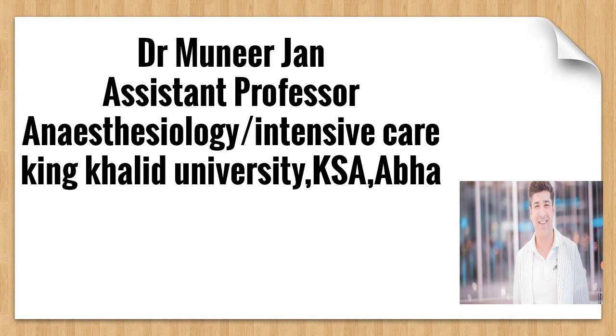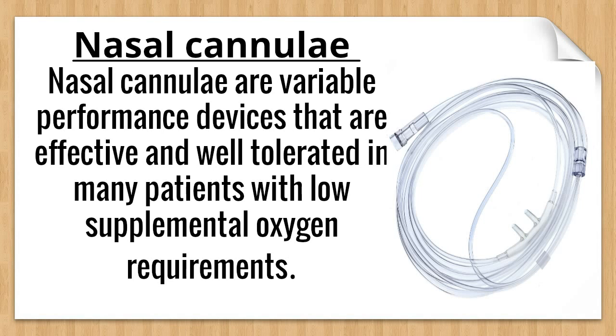We will be discussing the advantages, disadvantages, and where you can use this nasal cannula, and of course how it works. Starting with the overview: nasal cannulas are variable performance devices, because you cannot predict how much percentage of oxygen you are going to deliver to the patient — it varies depending upon the respiratory rate of the patient and other factors.